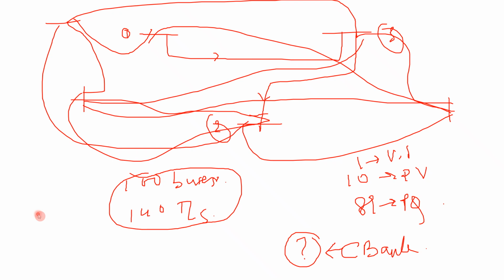It is not that you connect to the grid, get the result, and observe, okay, these buses need a capacitor bank, then I will order capacitor banks from the vendors, they will give me quotations, then I will purchase them, then I will put them in. No, before charging the power, you have to do all these things beforehand, because if you charge the power and the voltage collapses, the system collapses, that will create a lot of economic loss. So as an engineer, you have to first do the calculations, then you can come to the conclusion that the power can be charged, because I have all this set up.